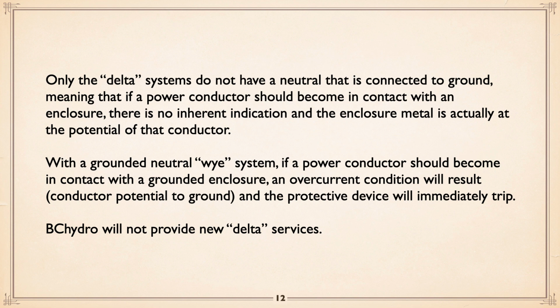Now, the delta system, as we say, does not have a neutral. What that means is if a power conductor should come in contact with a metal enclosure, there is no inherent indication, and the enclosure metal is actually at the potential of that conductor. Let's say that's happened: a line has come in, it's worn through, and the conductor is touching a kiosk or whatever. And you walk over and you lean on the kiosk. You might as well be leaning on one of the three hot wires coming in.